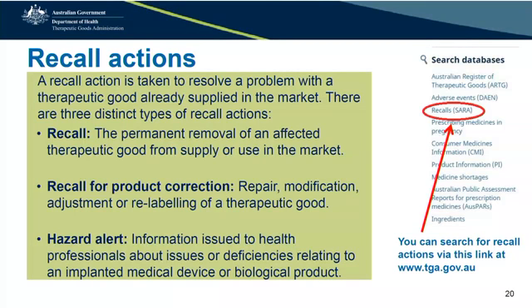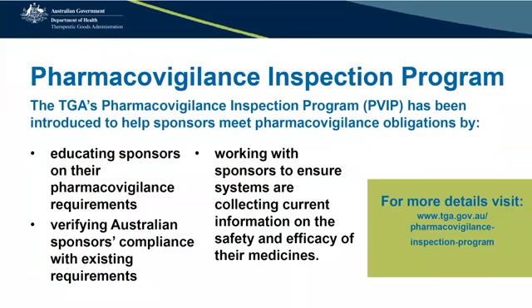So recall is a permanent removal of an affected therapeutic good from supply or use on the market. Then we have recall for product correction, where they repair, modify, adjust, or relabel a therapeutic good. So a common one might be where it doesn't have to be bad, it can be good. Sometimes they extend the shelf life of the product, and then they recall all their devices that they have, and they relabel them with the extended shelf life. And it could be a hazard alert. Information issued to health professionals about issues or deficiencies relating to an implanted medical device or biological product. So this happened with the meshes because you couldn't exactly take them out. Right, so even though they recalled the device, there had to be a hazard. Initially, it was a hazard alert that was issued. Then it was a recall, but a lot of the time, if something's been used, you issue both of them together. Okay.